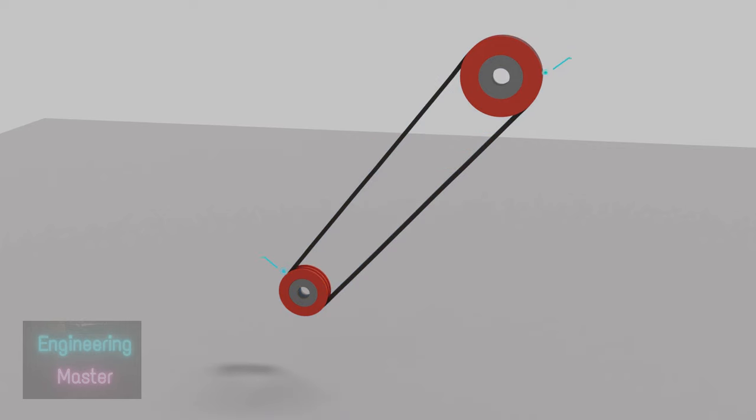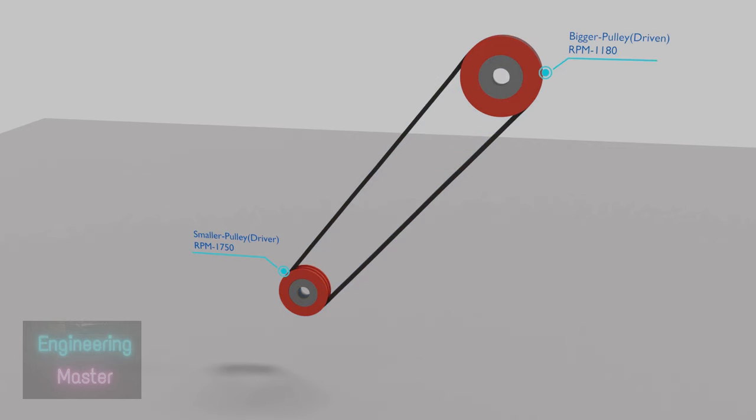In the belt and pulley power transmission system, belts are used to transmit power from one shaft to another by means of pulleys, which rotate at the same speed or at different speeds. Here belt and pulley power transmission is used to rotate impeller at a lower speed than the motor. To make impeller speed less than the motor speed, the driven pulley should be bigger than the driver pulley.